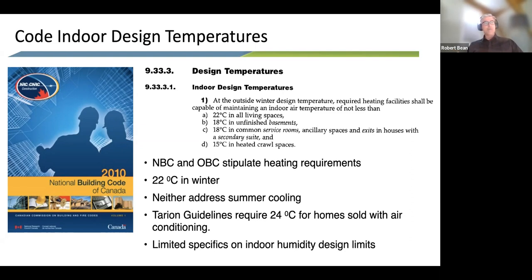A lot of people will talk about ASHRAE, and you're going to do this in a minute or two - it talks about the restrictions, but the reality is there's a large band you can use in a space for comfort. Because there are so many metrics, if you have a drop in air temperature, you have to compensate with a higher MRT. So it's a balancing act. This number gets you started, but it's definitely not a representation of comfort.